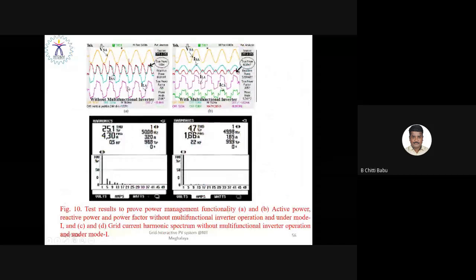And see the active power sharing and the THD of the grid current. Without any controller, the THD would be around 25.1%, but with active current control, the THD has been reduced to 4.7%. Moreover, it injects only sinusoidal current into the utility grid, with negligible harmonic current injection.